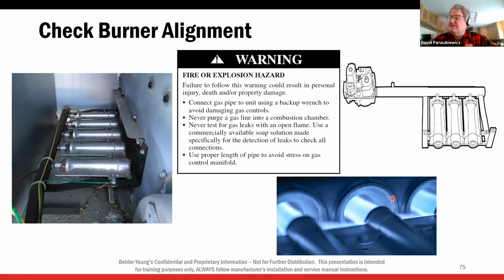The alignment of these burners is everything. Right here, you can see there's no impingement. You'll see this impingement start here to where this is rusting here, or you can see the burners were hitting off that target. All right, that's definitely a burner alignment. So that's something we need to address if you see it. And again, when you're piping it, that's what causes the problem. We put too much pressure on that gas piping, and we bend the valve up or down. We bend the burners up or down. So there shouldn't be any torque on that gas pipe at all.